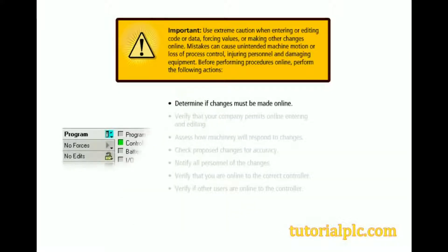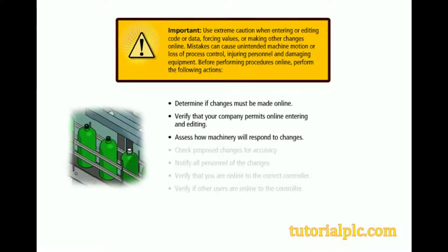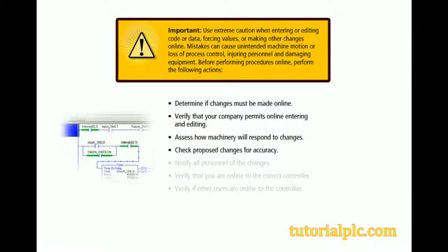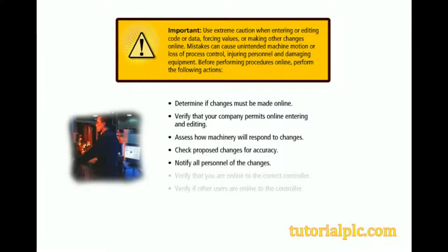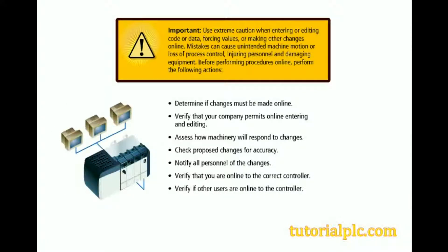Determine if changes must be made online. Verify that your company permits online entering and editing. Assess how machinery will respond to changes. Check proposed changes for accuracy. Notify all personnel of the changes. Verify that you're online to the correct controller and verify if other users are online to the controller.